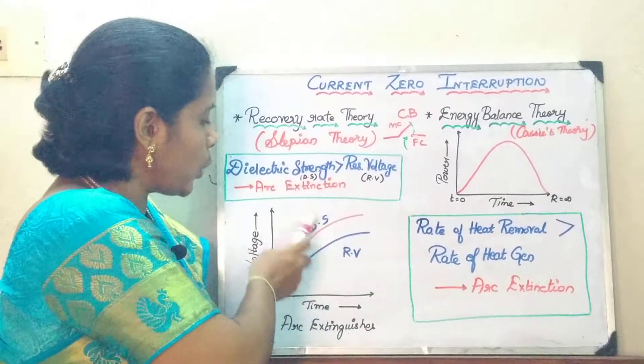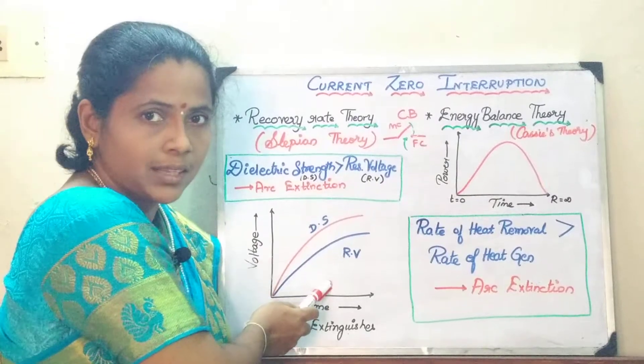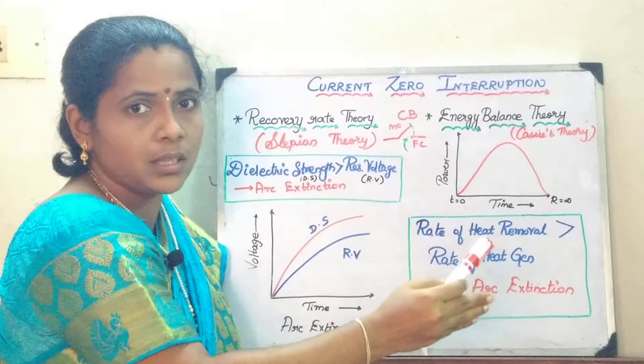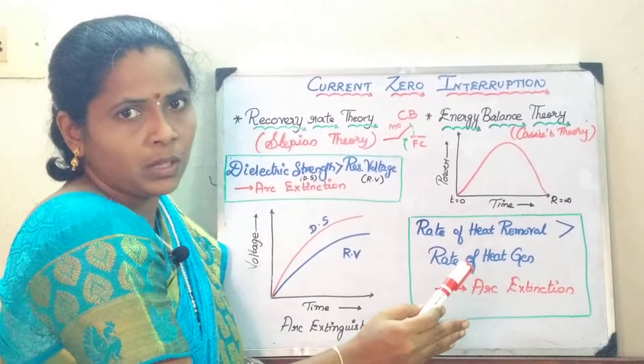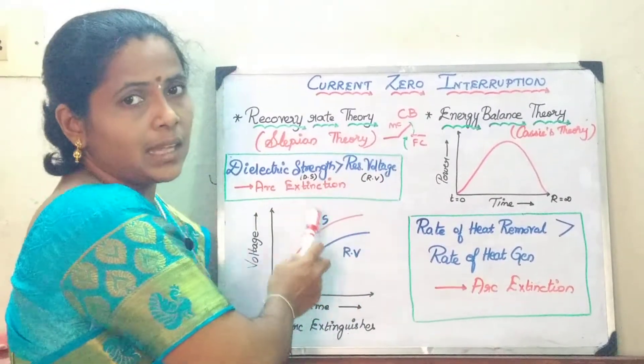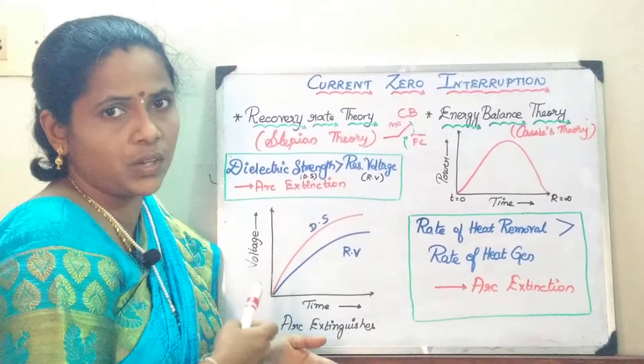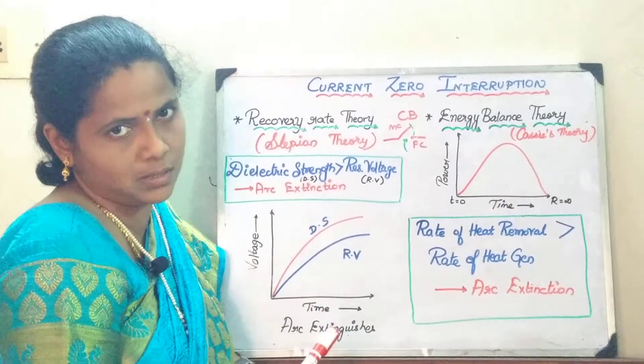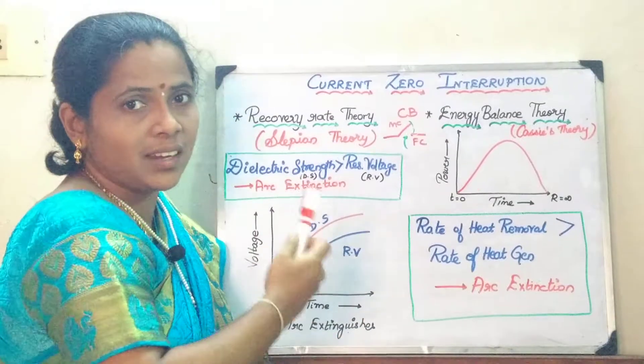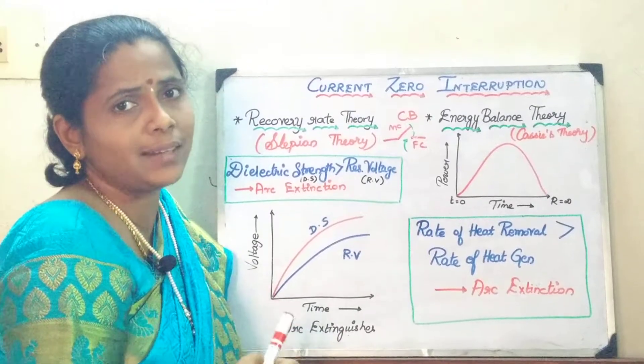Suppose the situation is vice versa — if the restriking voltage is going to be more than your dielectric strength, then the arc will restrike again, and it will take one more half cycle to quench the arc when it reaches current zero. So to summarize: if the dielectric strength is greater than the restriking voltage, the arc will get extinguished; if the restriking voltage is greater than the dielectric strength, the arc will persist. The rate at which the dielectric strength is getting recovered with respect to the restriking voltage is called the recovery rate theory.